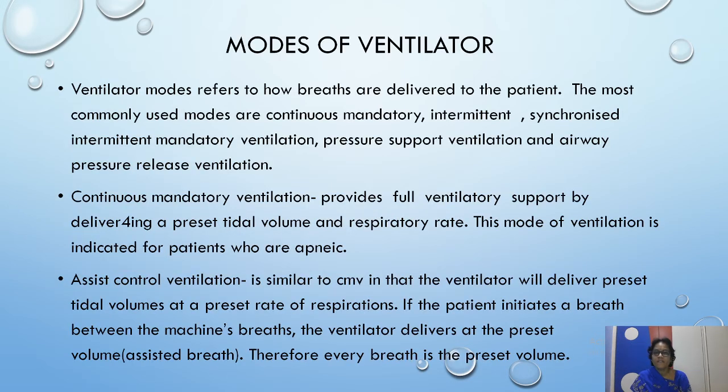Next, what are the different modes of ventilators? What is a ventilator mode? It refers to how breaths are delivered to the patient. The most commonly used modes are continuous mandatory ventilation, assist control ventilation, intermittent mandatory ventilation, synchronized intermittent mandatory ventilation, pressure support ventilation, and airway pressure release ventilation. What is continuous mandatory ventilation?